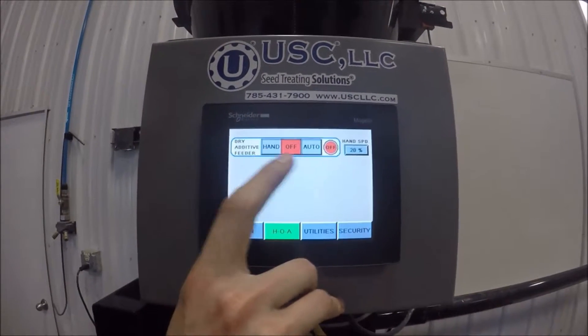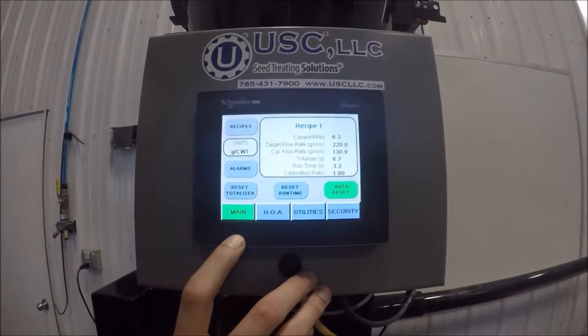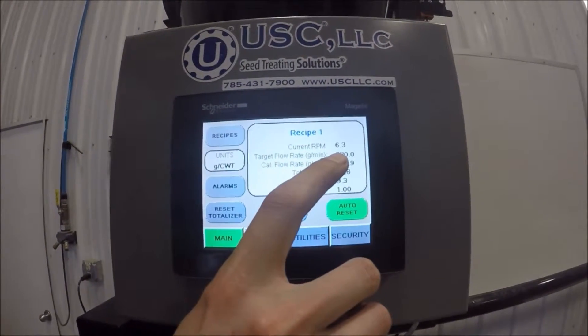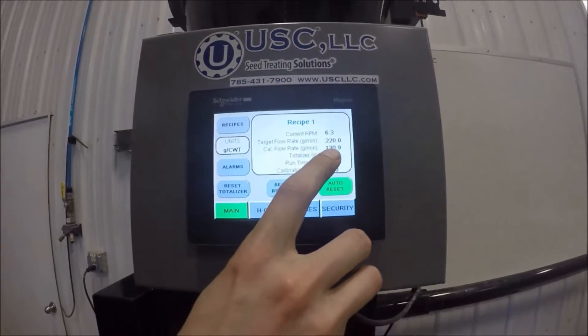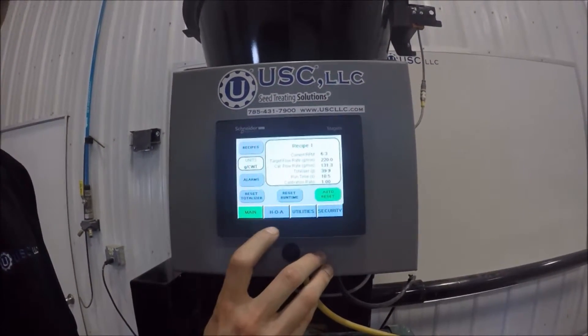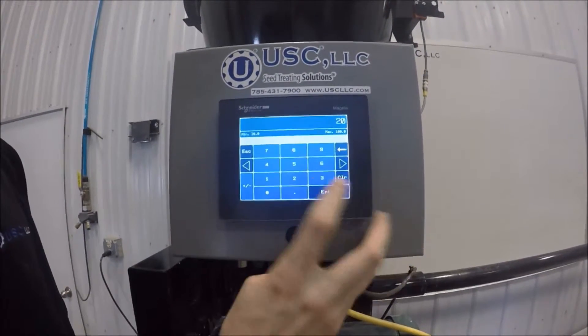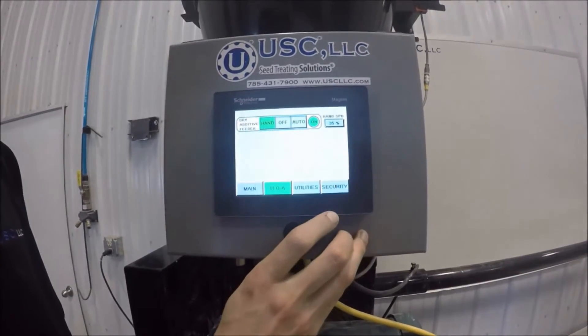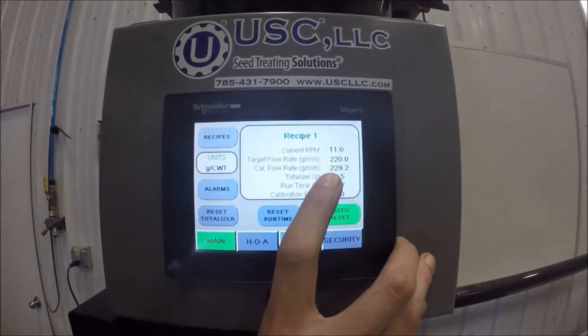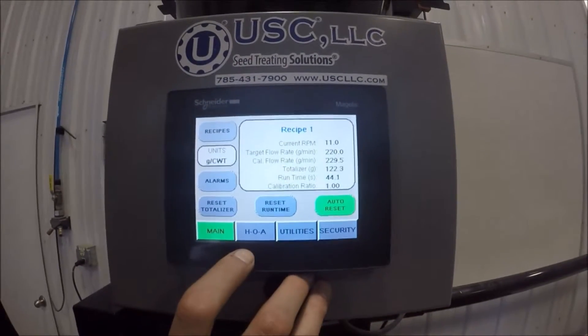We'll go back to the HOA screen. Set it at 20% and turn it on by hand. At this point we can see that our current flow is at 130 and we need to be at 220, so we can adjust the speed up to match that flow rate. From the HOA screen, we adjust that percentage from 20 up to 35. When we go back to the main screen, we'll see that the calculated flow rate adjusted up to 229, which is very close to the 220 we're looking for. So at this point we're ready to calibrate.